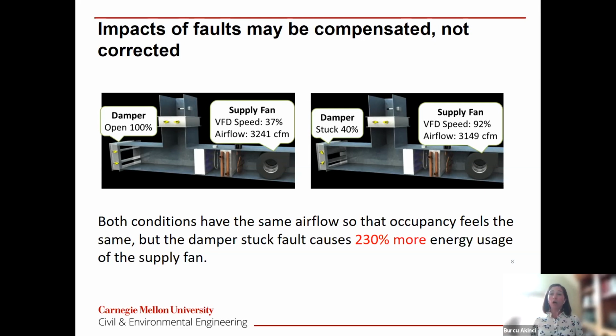From the occupant's perspective, there's no difference — no symptomatic issue here, so nobody will say there's a fault in the system because the airflow comes the same way in both scenarios. But what's happening behind the scenes is that you're utilizing at least twice as much energy to provide the same airflow, because there's a fault here that is not detected.